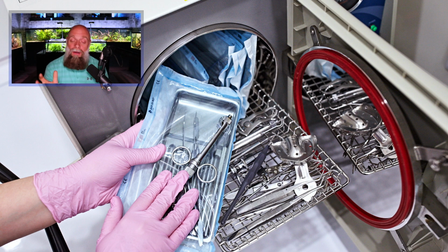And so often with an autoclave, we are heating things to 121 degrees or around 120 degrees Celsius. We're using high pressure, 15 psi, and we're usually keeping those parameters somewhere around 15 to 20 minutes. And when we do that, it generally wipes out just about everything with the exception of those infectious proteins called prions. But viruses, all types of bacteria, endospores, all gone.